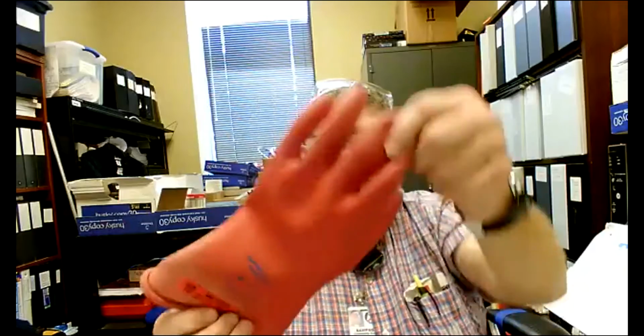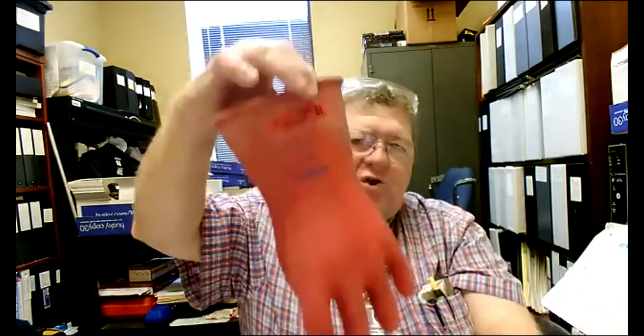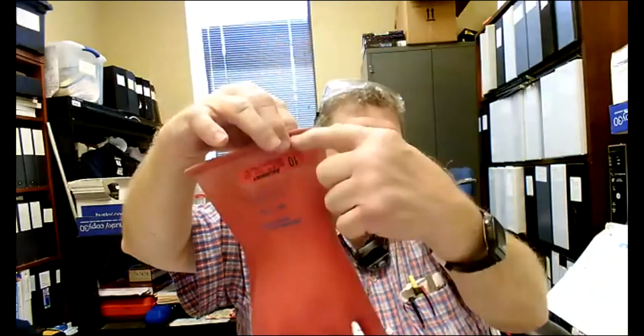The leather doesn't give you the electrical protection. It gives you abrasion protection so that you don't tear the rubber part. So the real listed part here, voltage wise, that protects you is the rubber part itself. And so you need both on. You may see in a video, or in some places, somebody using these by themselves, but it's far better to use them as a pair like it's supposed to be done, with the leather on top. It's very cumbersome, but that's the safest way to do it. Now, when I send these off to a lab in Goldsboro to get them checked, they check them with a high pot. I believe they're submerging them in water and checking them that way. They check for pinholes all the way from the tip of the finger up to here.